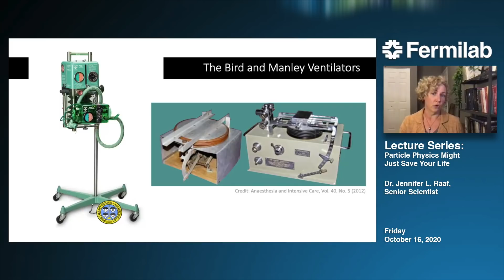The ventilator that we've designed during this pandemic is modeled after these two original machines. It has no motors or pumps. It just needs a source of pressurized air and oxygen, but it's electromechanical instead of fully mechanical. So it also needs an electrical outlet. The modern day upgrade of our machine is that the opening and closing of valves is initiated by a microcomputer.